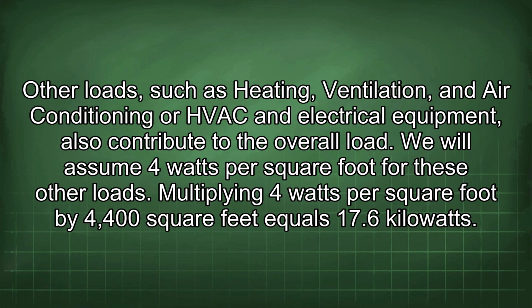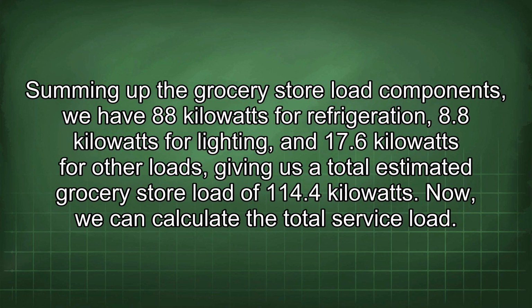Other loads, such as heating, ventilation, and air conditioning, or HVAC, and electrical equipment, also contribute to the overall load. We will assume 4 watts per square foot for these other loads. Multiplying 4 watts per square foot by 4,400 square feet equals 17.6 kilowatts. Summing up the grocery store load components, we have 88 kilowatts for refrigeration, 8.8 kilowatts for lighting, and 17.6 kilowatts for other loads, giving us a total estimated grocery store load of 114.4 kilowatts.